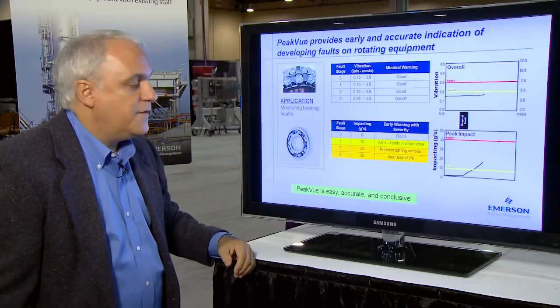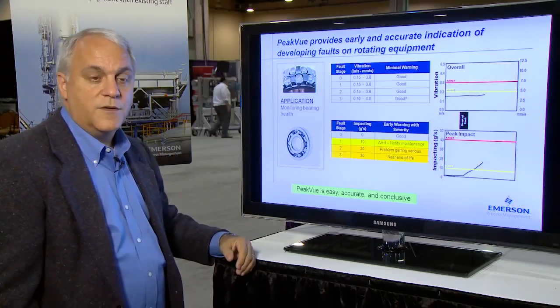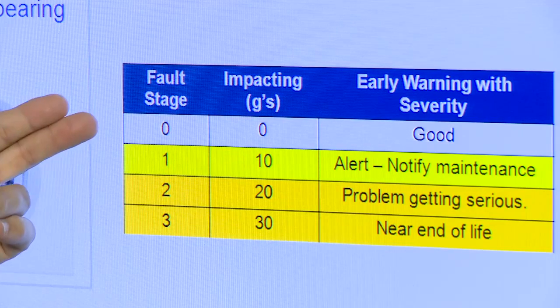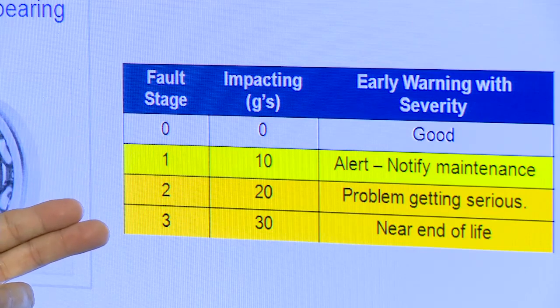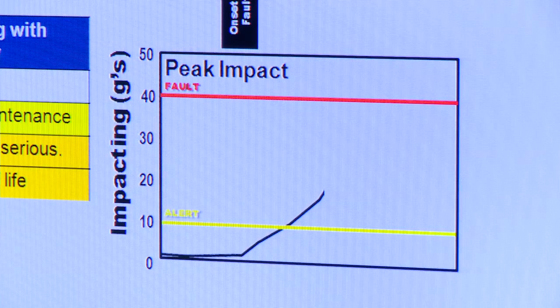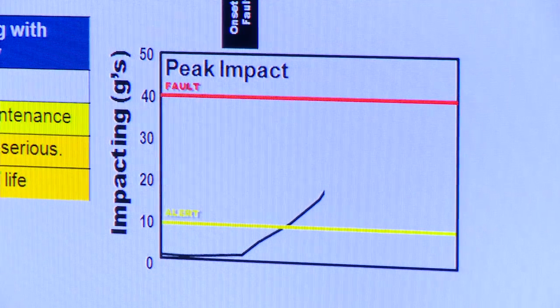In contrast, if you look at Emerson's patented PeakVue measurements, you'll see that as we move through the three stages of bearing failure, the PeakVue impacting levels measured in G's increase proportionately. And in the trend, it's very clear to see that the level rises from zero towards a significant amplitude.